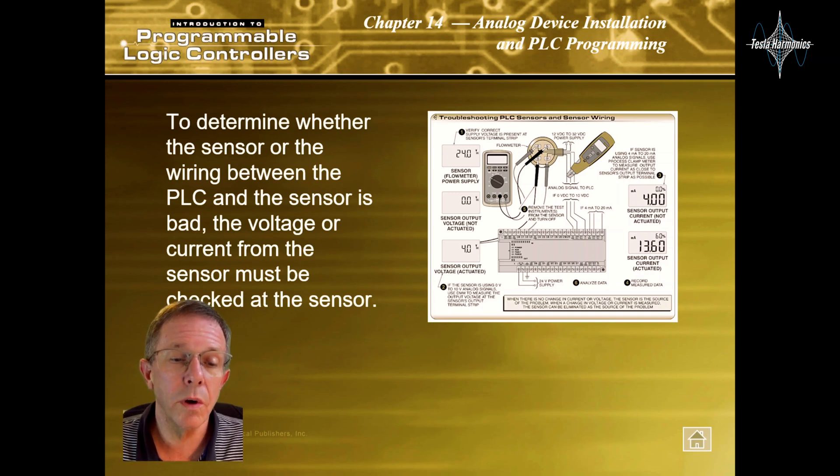To determine whether the sensor or the wiring between the PLC and the sensor is bad, the voltage or current from the sensor must be checked at the sensor.